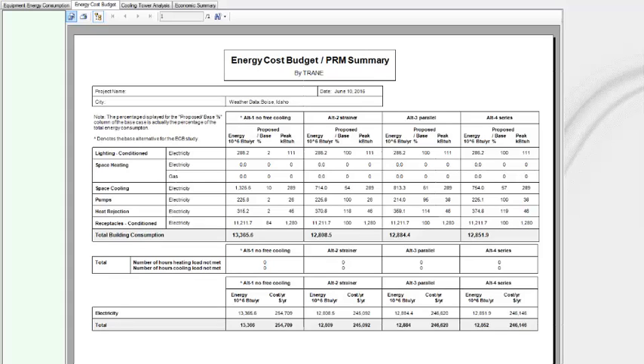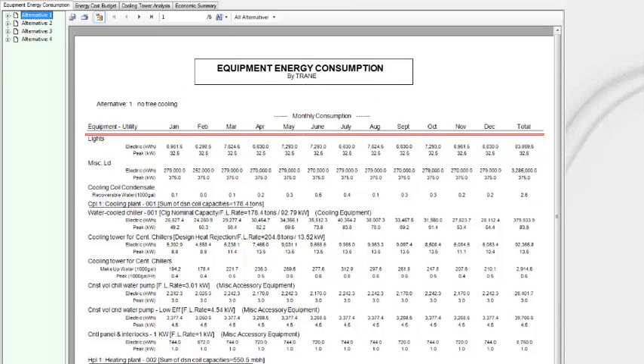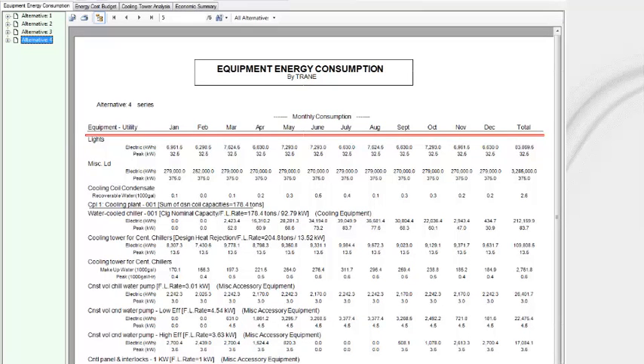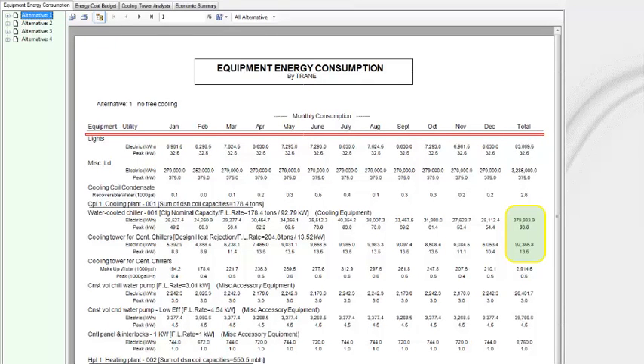If you want to know when the free cooling is benefiting the chiller, you should check the Equipment Energy Consumption Report. In this case, I can quickly go between the alternatives using the tree on the left-hand side of the screen to quickly compare the annual chiller consumption of each alternative. Take note of the annual consumption values for the chiller and the tower as I switch between alternatives. For no free cooling, the chiller consumption is about 380,000 kWh and the tower used around 92,000 kWh. There's cooling in the winter season as well — look at January: 26,000 kWh.